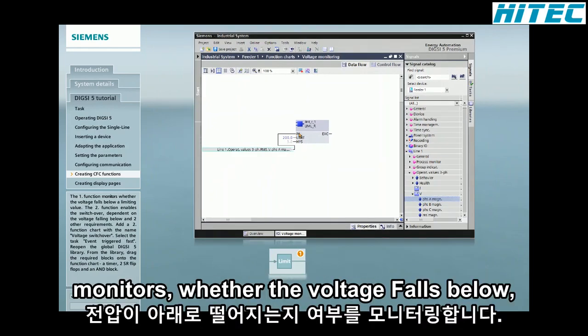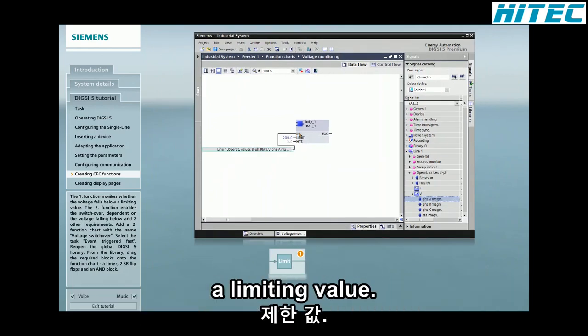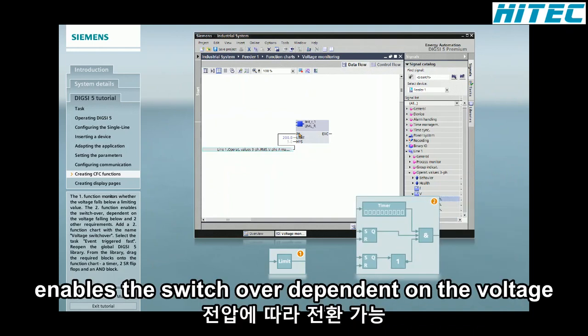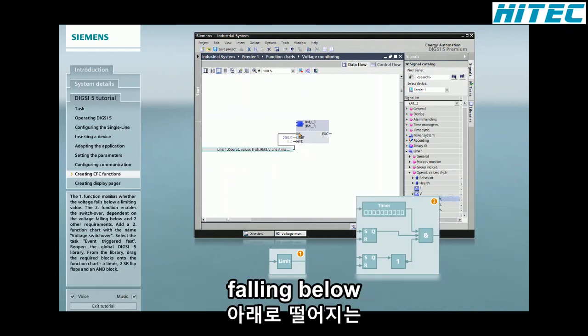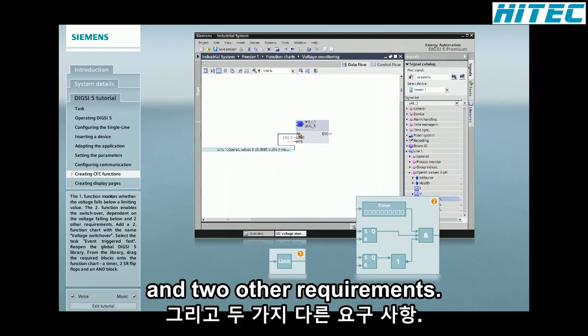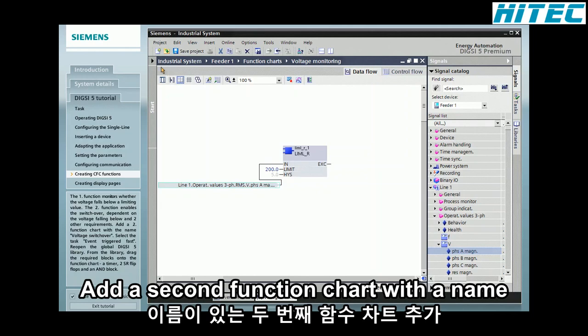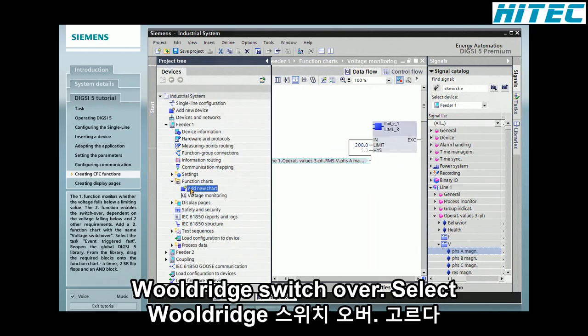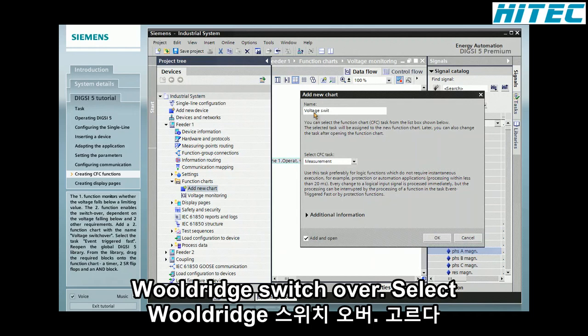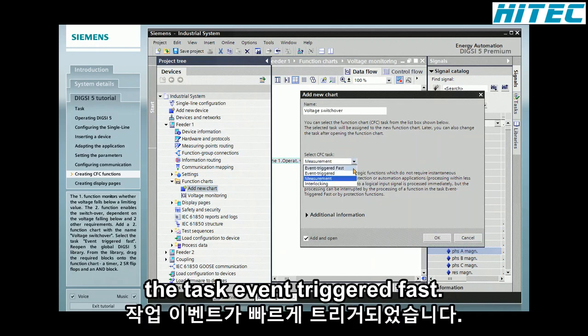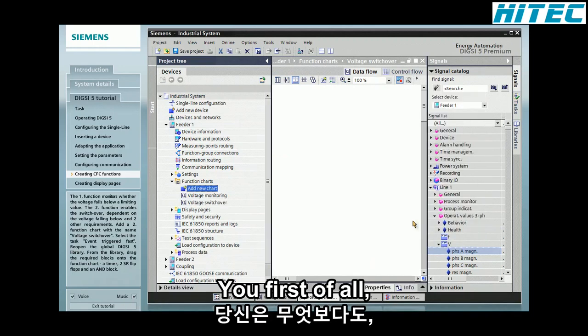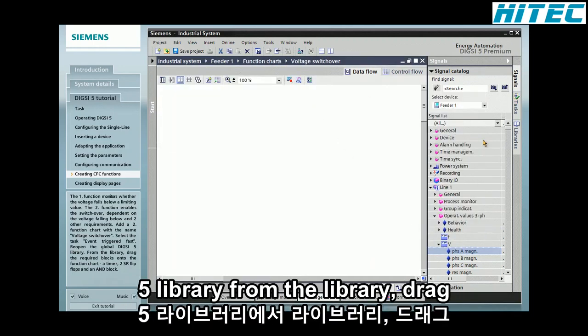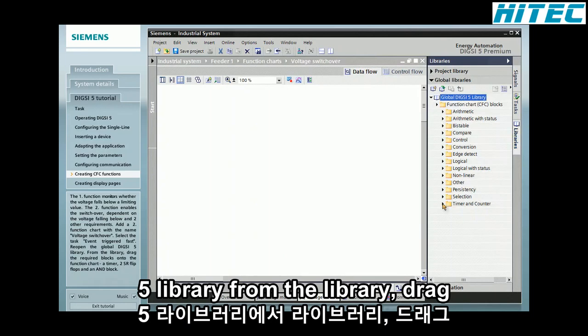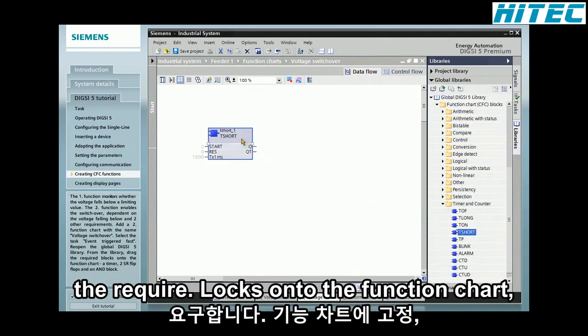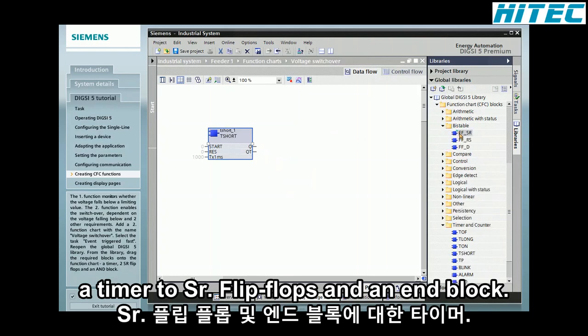The first function monitors whether the voltage falls below a limiting value. The second function enables the switchover dependent on the voltage falling below and two other requirements. Add a second function chart with the name Voltage Switchover. Select the task Event Triggered Fast. You first of all have to reopen the global DIGSI 5 library. From the library, drag the required blocks onto the function chart, a timer, 2 SR flip-flops, and an AND block.